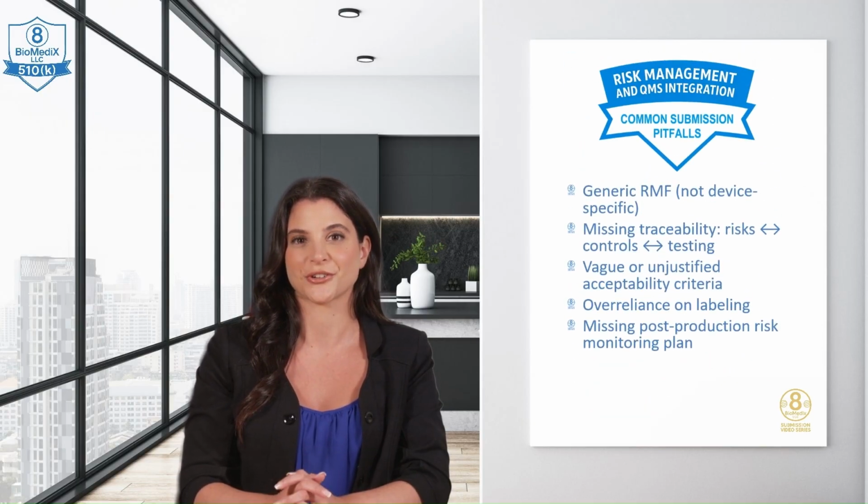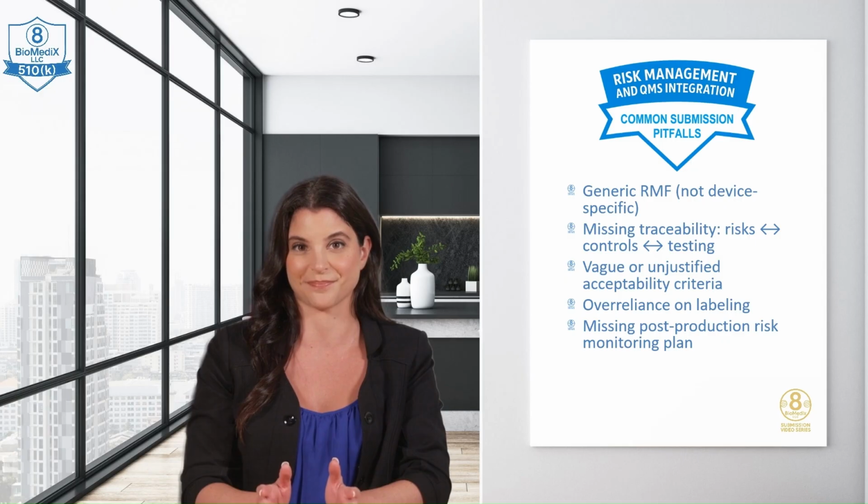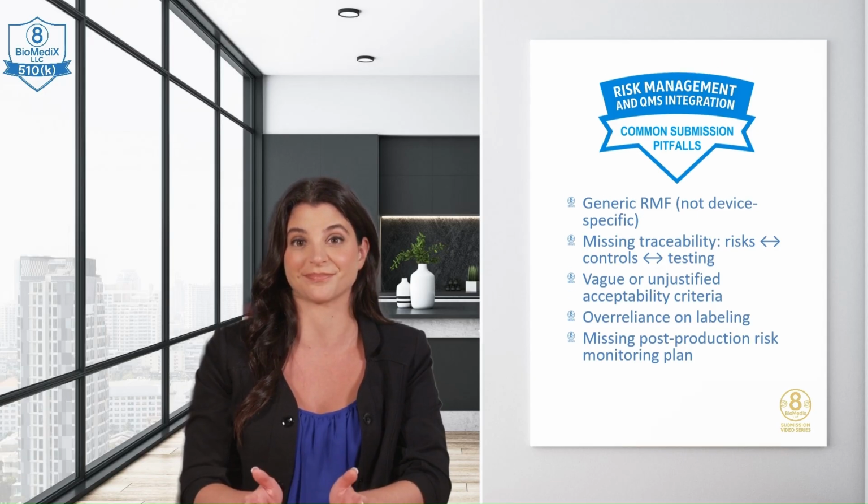Common pitfalls in risk management and QMS for submissions. Common pitfalls include submitting a generic RMF not specific to the device, lack of traceability between risks, controls, and design testing data, undefined or unjustified risk acceptability criteria, over-reliance on labeling rather than design or protective controls, and failure to include a post-production risk monitoring plan.